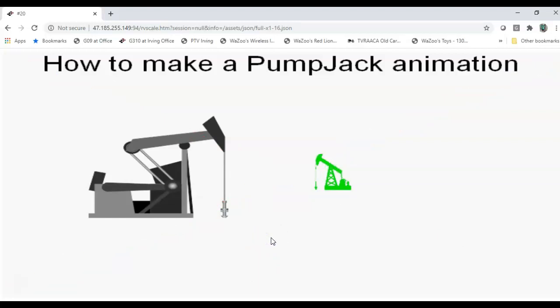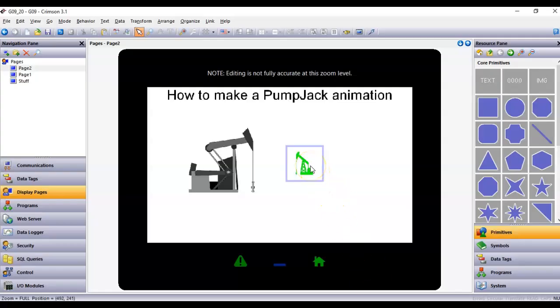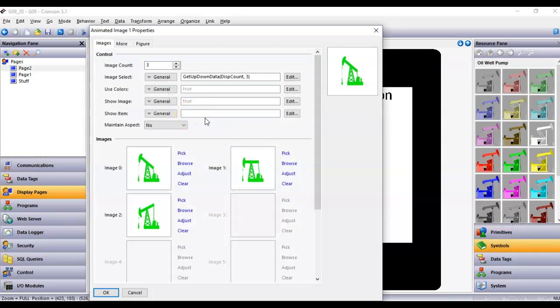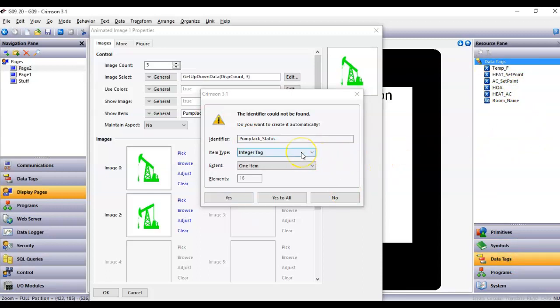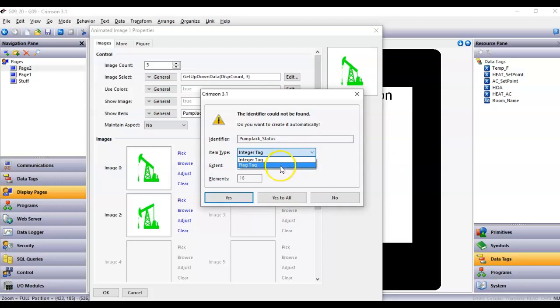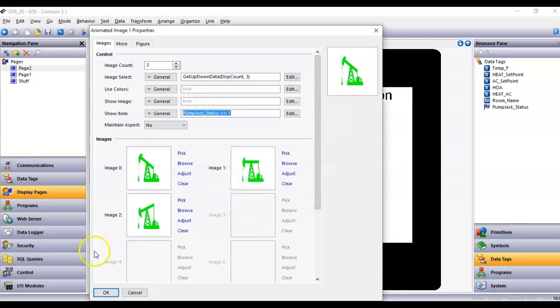Now what if I wanted this picture to only show up when the pump jack is running? Right here I can create a tag — let's call it pump_jack_status. I'll use two equal signs and the value 1, asking: if the pump jack status tag equals 1, show this; otherwise it won't show up. It's going to ask me to declare that tag. I want it to be an on/off thing, so instead of an integer I'll allocate it as a Flag tag — the boolean type — and click OK.